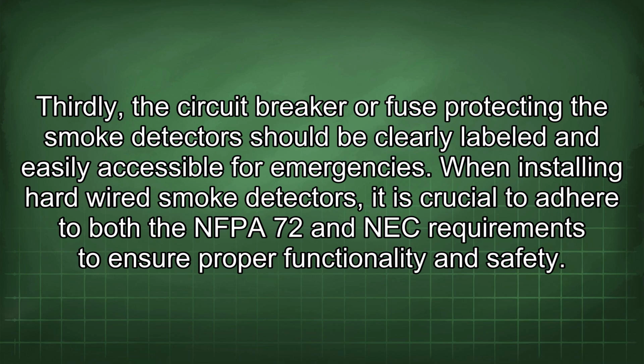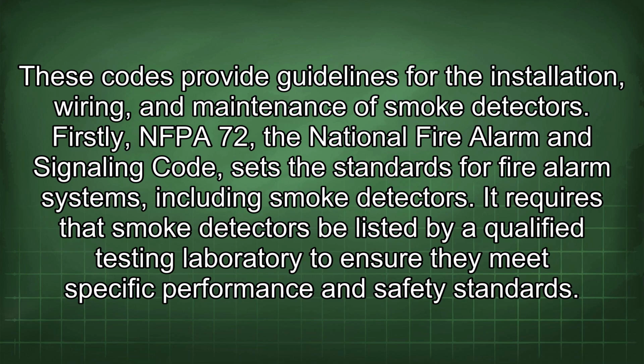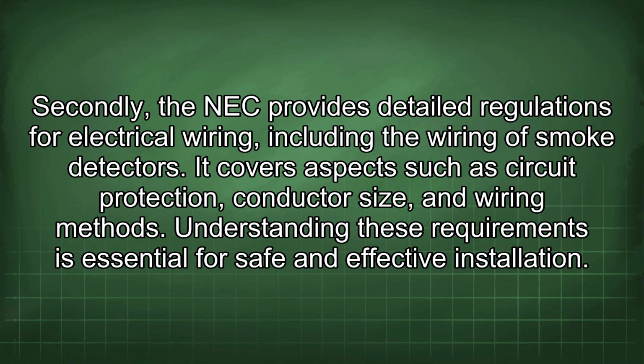When installing hardwired smoke detectors, it is crucial to adhere to both the NFPA 72 and NEC requirements to ensure proper functionality and safety. These codes provide guidelines for the installation, wiring, and maintenance of smoke detectors. Firstly, NFPA 72, the National Fire Alarm and Signaling Code, sets the standards for fire alarm systems, including smoke detectors. It requires that smoke detectors be listed by a qualified testing laboratory to ensure they meet specific performance and safety standards. Secondly, the NEC provides detailed regulations for electrical wiring, including the wiring of smoke detectors. It covers aspects such as circuit protection, conductor size, and wiring methods. Understanding these requirements is essential for safe and effective installation.